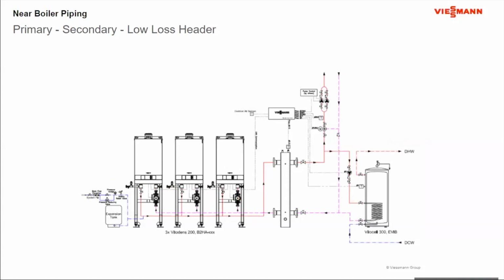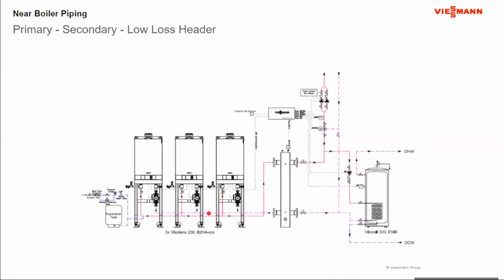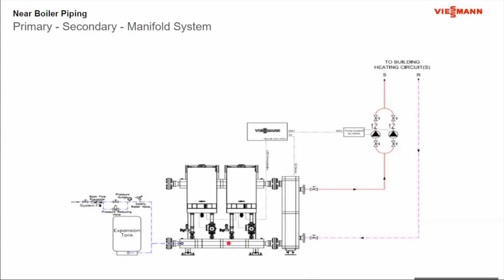Okay, reverse return piping is paramount if I have a single pump trying to pump through 2, 3, 4 boilers. But here, because each boiler gets a pump, I'm not worried, and as long as I properly size these header pipes, reverse return isn't required. I should see balanced flow through each one of the boilers. But again, the key is the fact that they each receive their own individual pumps. So I see individual pumps here. I see individual pumps here per boiler. But the other key is the manifold system has to be short, and it has to be sized properly for a very low pressure drop to keep it balanced. Okay.